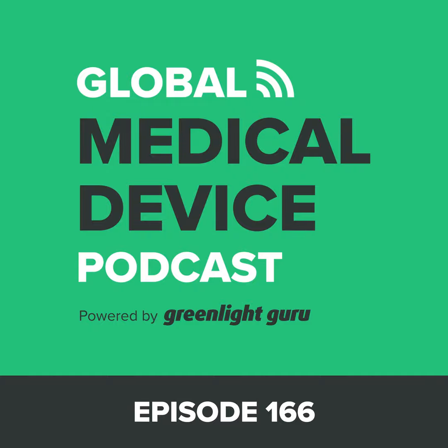But I always find it interesting, John, working in the gray area. For example, I've had situations where a device is in contact with a patient for some period of time, and then it's not. And then it comes in contact with the patient again for a period of time, and then it's not. Those kinds of situations don't fit easily into one of those buckets. And that's up to us to figure out how to apply it. So it's those gray areas. Another gray area is, what if the person is wearing clothing, or what if they have hair or sweat? How can that interfere? So again, that's all part of the calculus here.